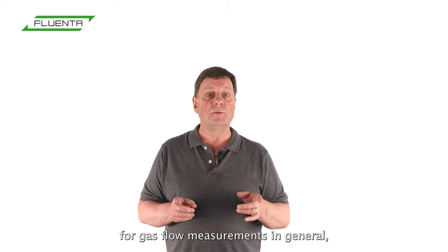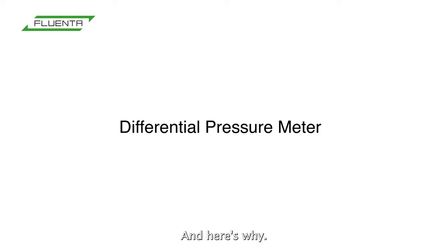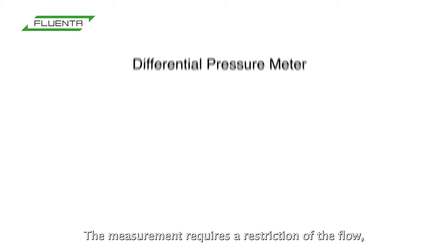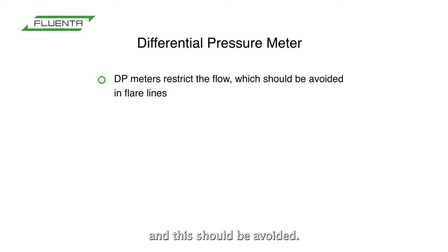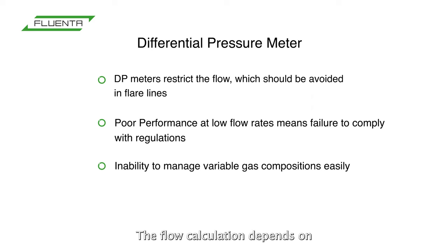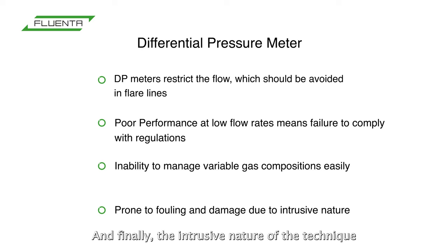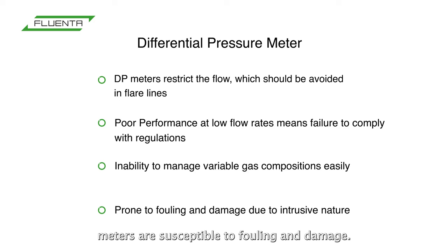While this technology is a popular choice for gas flow measurements in general, it's not always suitable for flare gas measurement. The measurement requires a restriction of the flow, and this should be avoided in flare lines. Poor performance at low flow rates means that the accuracies required by legislation cannot be met. The flow calculation depends on gas density and hence gas composition, so varying gas compositions as found in flare lines are a challenge. The intrusive nature of the technique means that differential flow meters are susceptible to fouling and damage.